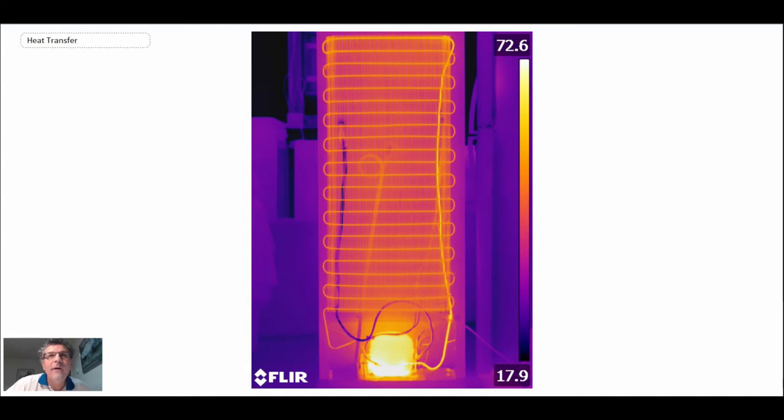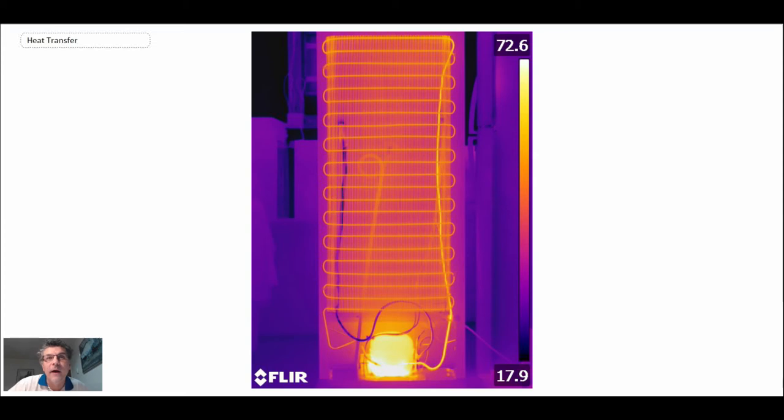That would be where you have condensation on the tube side. The condensation is occurring within the tube. It's going from being a superheated vapor down to the saturation temperature, and then it would go through a phase change, and then you would have a liquid coming out at the bottom. That is typically the cycle used for any kind of refrigeration system.